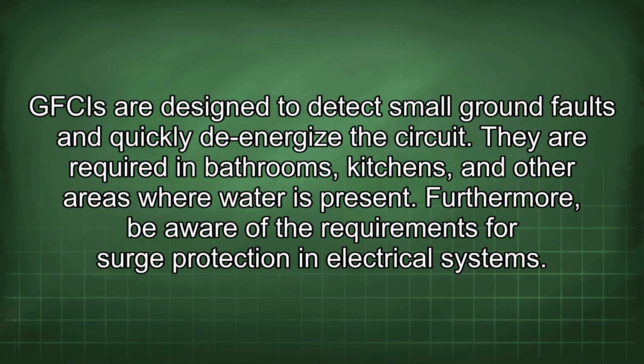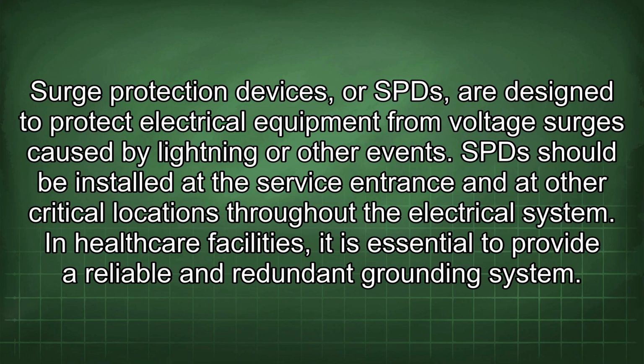Furthermore, be aware of the requirements for surge protection in electrical systems. Surge protection devices, or SPDs, are designed to protect electrical equipment from voltage surges caused by lightning or other events. SPDs should be installed at the service entrance and at other critical locations throughout the electrical system.